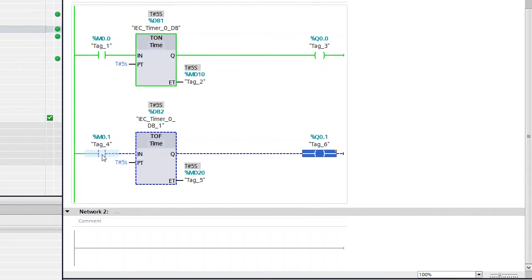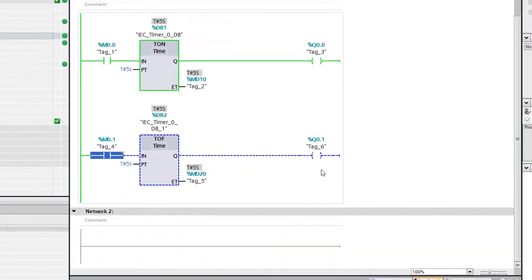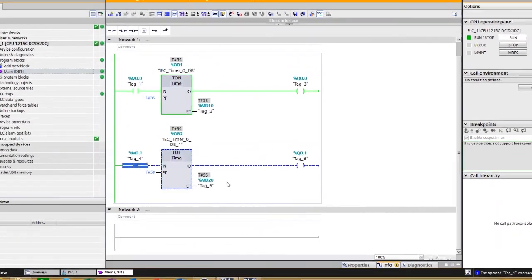The off-delay timer is triggered only when the input goes OFF. When the input is high, the output is ON. The moment I switch the input to 0, the timer starts — two, three, four, five — and the output goes OFF. Now you can see the difference between TON and TOF: TON is the on-delay timer and TOF is the off-delay timer.